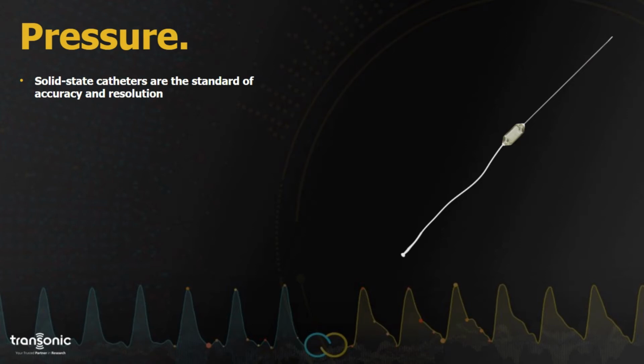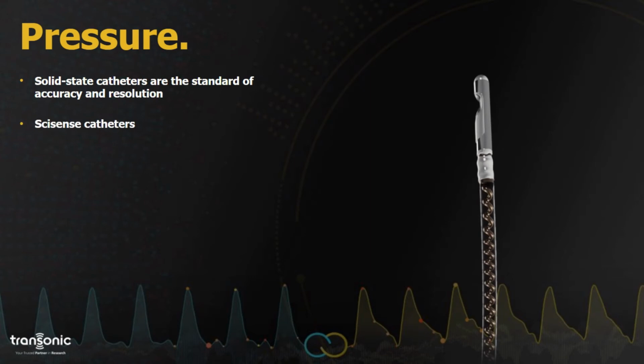Every single provider provides some form of a pressure measurement device, though some providers measure these things in different ways. Of these methods, the accepted gold standard of accuracy and resolution, and has been for decades, is a solid-state high-fidelity catheter. However, the problem with these catheters is that they're very challenging to manufacture due to their extremely small size, sensitive components, and therefore the specialized expertise needed to build them. So what we'd like to do is reintroduce the SciSense brand. The SciSense brand has been proud to manufacture solid-state catheters for the past 20 years. As many of you on this call will know, we're known for our admittance technology. This is a technology that allows you to measure pressure volume loops and get volume live without complicated calibration steps.